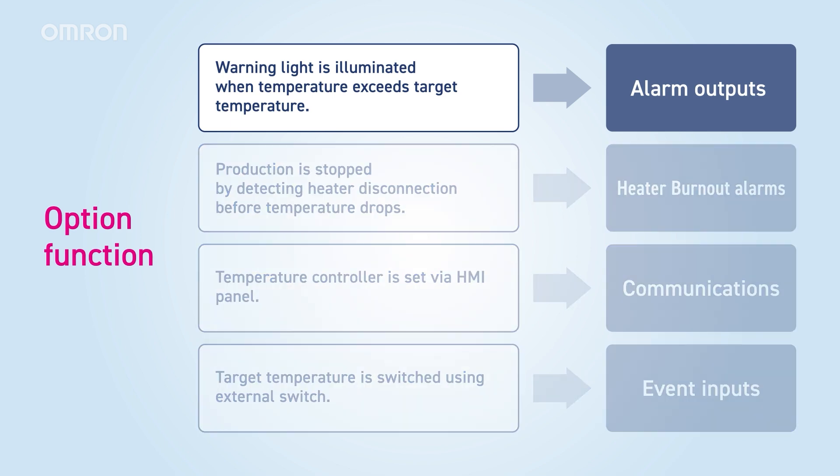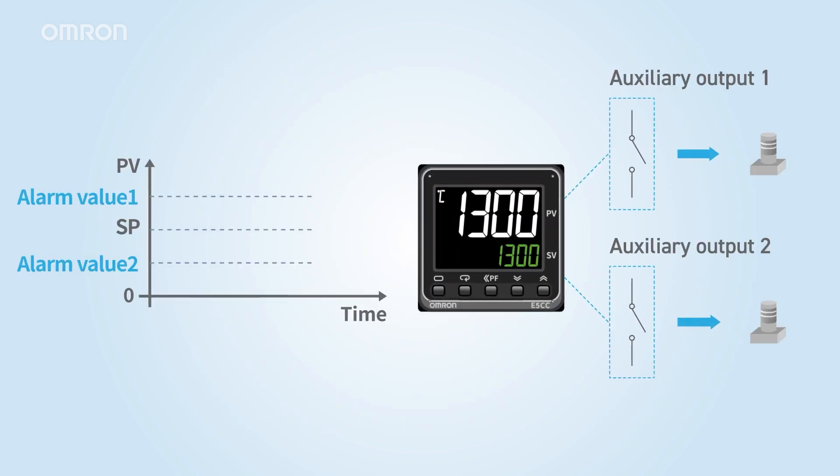First, look at the alarm outputs that detect temperature anomalies. When the current temperature deviates from the specified range, an alarm is triggered via a relay signal from the auxiliary output terminal. This signal can be used to stop the equipment or to activate a warning light.